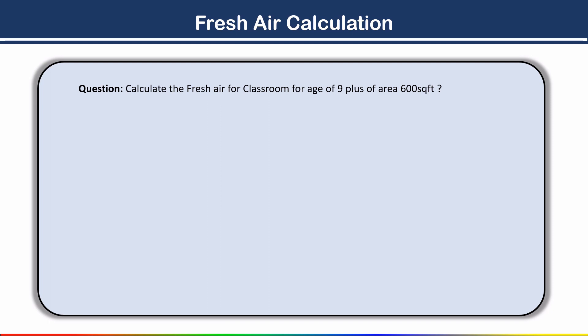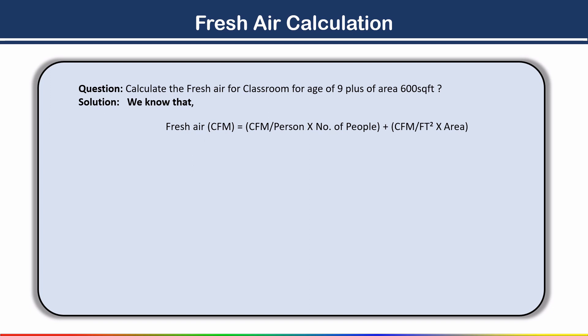Now here I have taken one example question to calculate the fresh air CFM. We have to calculate the fresh air for a classroom for age 9 plus, with an area of 600 square feet. So here we have a classroom where age 9 plus students are sitting and the total area of that classroom is 600 square feet. To find out the fresh air CFM, we use the ASHRAE ventilation standard formula: Fresh Air CFM.